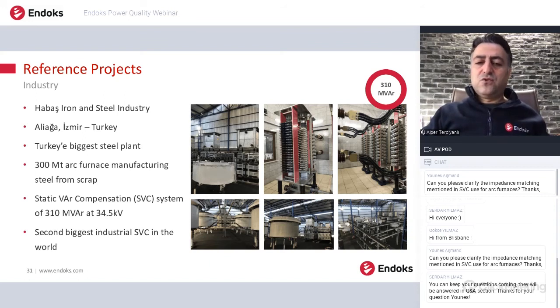In arc furnace applications, we are mostly using second, third, fourth, fifth, and sometimes higher harmonic filters in order to eliminate harmonics. And these are fixed banks. In the system, we have a 300 MVAr fixed capacitor bank, and also we have a 310 MVAr variable shunt inductor, which is controlled by thyristor valves. So we can control the reactive power from 0 to 310 MVAr in a continuous way with 10 millisecond resolution. So it is very important. By the way, in many countries, using SVCs along with arc furnaces is compulsory. You must use an SVC with the arc furnace because of grid codes.